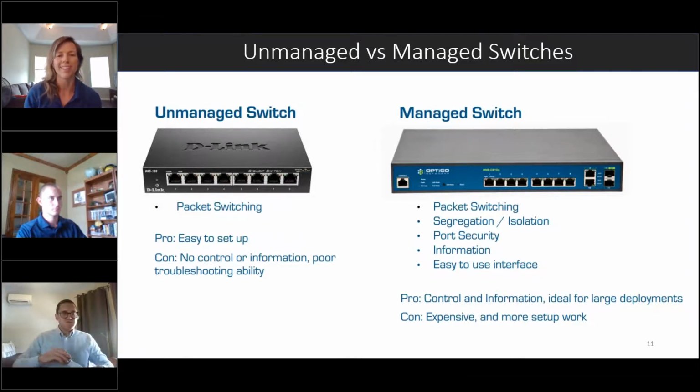Yeah, in one of our previous sessions, Grant and I really described the differences from MSTP controllers to IP controllers, and a lot of differences, including communication speed being one of them. However, some lessons learned I know our system integrators have experienced: I've heard of some attempts where our BAS contractor put in unmanaged switches and was wondering why their IP-based controller system was slow and clumsy. After our support engineer helped them with some troubleshooting, we realized they had installed all unmanaged switches and things weren't working properly.